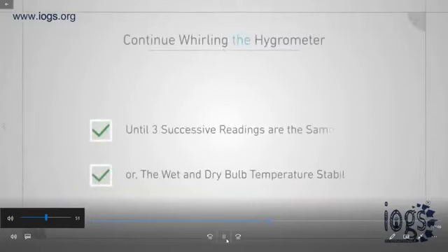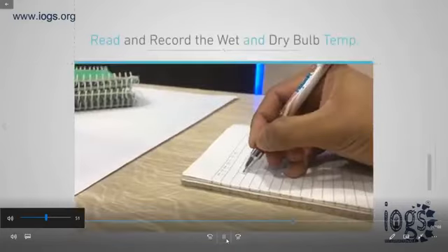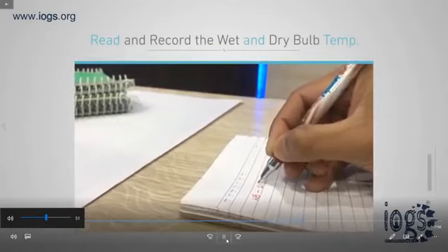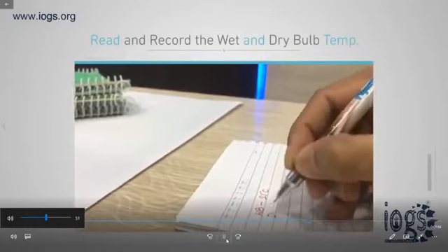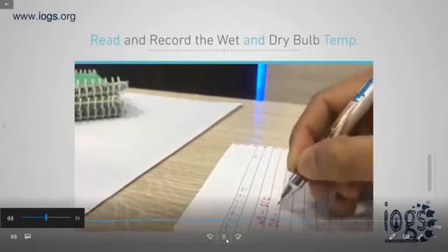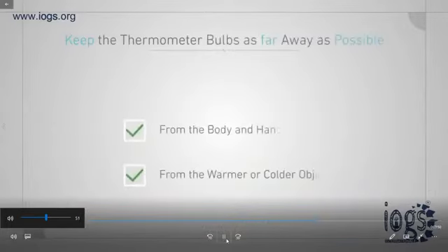Continue this system of whirling until 3 successive readings are the same or the wet bulb temperature becomes stable. When the temperature stabilizes, read and record first the wet bulb temperature. Next, read and record the dry bulb temperature.